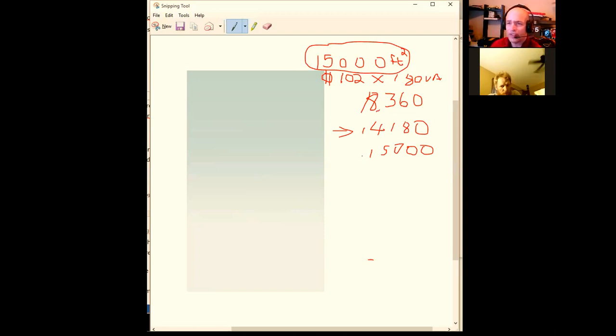those are probably, I've never seen a question where they didn't reach enough to hit you over this 10K mark, that's the table on the next page of text. So you're going to want to derate anything that hits 10K or above, but it has to meet 10K in its own section. In other words, you don't want to put section 1 on top of section 2 and then take the derates under the table on the next page. Section 1 has to make 10,000 all by itself before you can derate it. Okay, yeah, so I had to do each one separate.